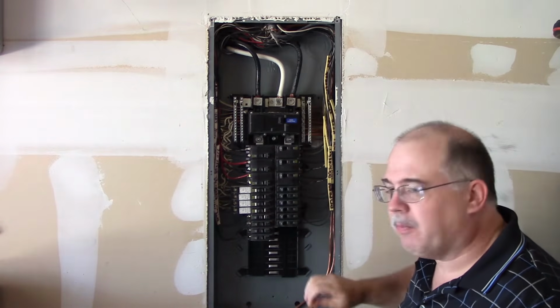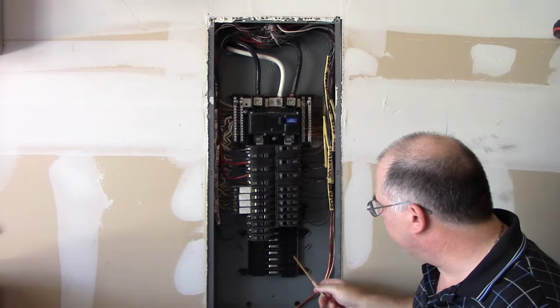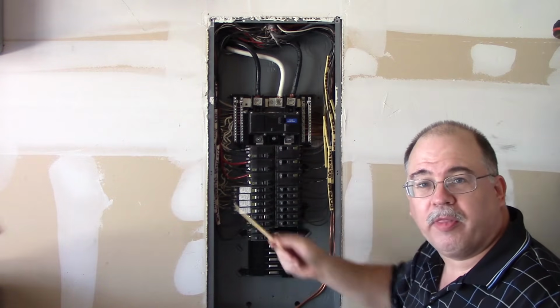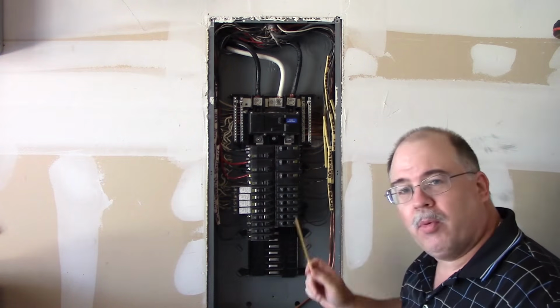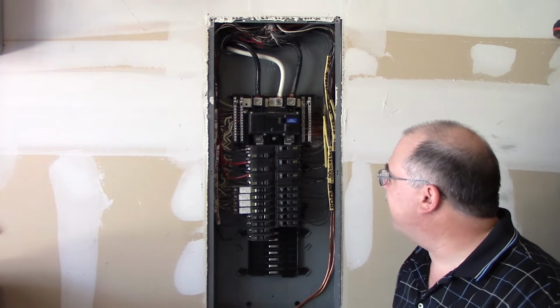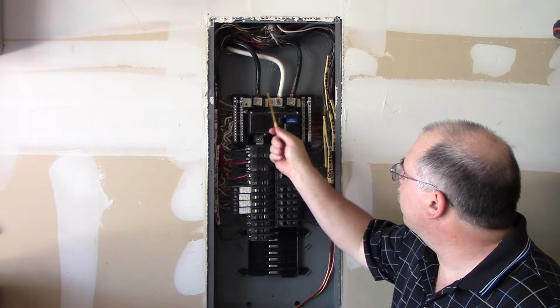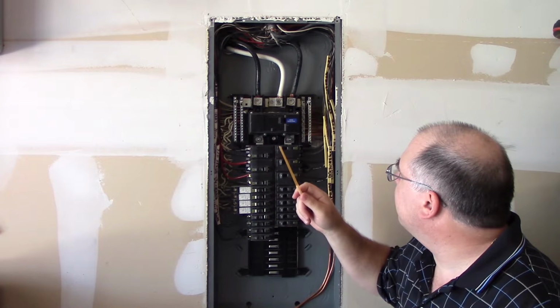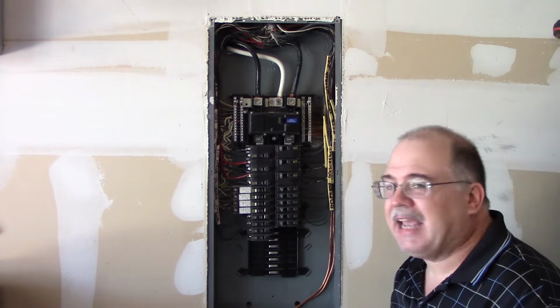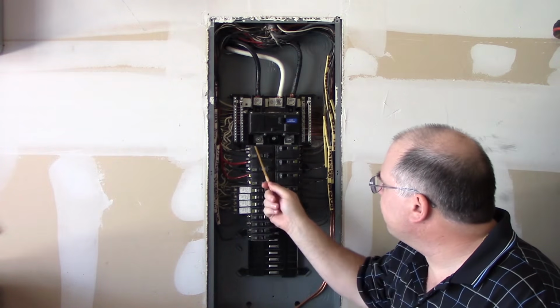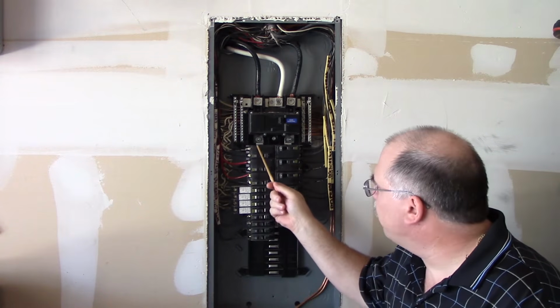Everything down here in the panel board itself, which is this component, this is actually the panel board. The whole thing is a cabinet with the panel board, or the guts as we call it, inside of it. Okay, so here are your lugs, and these here are Allen wrench lugs or mechanical lugs. This is a 2-pole circuit breaker, or a double pole.